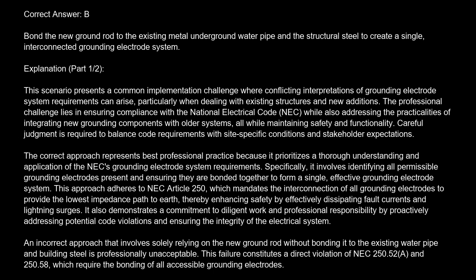The professional challenge lies in ensuring compliance with the National Electrical Code, NEC, while also addressing the practicalities of integrating new grounding components with older systems, all while maintaining safety and functionality. Careful judgment is required to balance code requirements with site-specific conditions and stakeholder expectations. The correct approach represents best professional practice because it prioritizes a thorough understanding and application of the NEC's grounding electrode system requirements. Specifically, it involves identifying all permissible grounding electrodes present and ensuring they are bonded together to form a single, effective grounding electrode system.